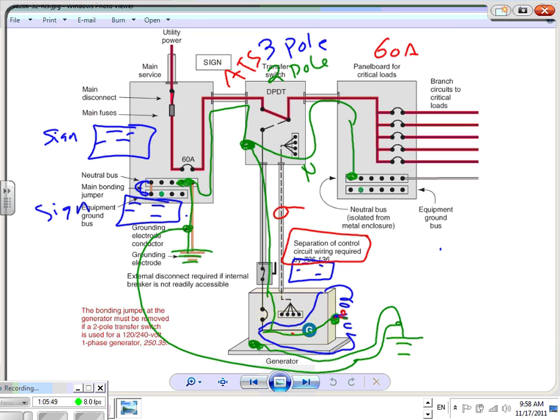Look at this. I have my auto transfer switch here and my generator. Can you see all these control wires here? There are sensors looking at the power coming from the utility. The minute it senses that there's no power right in here, it sends the signal through these wires directly to the generator to start. If it's manual, it doesn't do anything; there's no control. If it's an auto, it sends a signal to the generator.